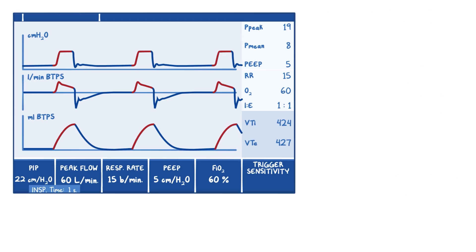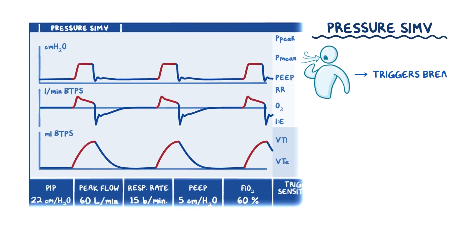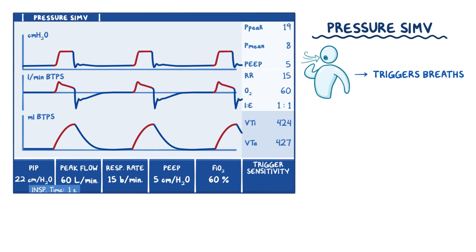So just like we were able to program the ventilator to support natural breaths in volume modes of ventilation, with pressure-synchronized intermittent mechanical ventilation, or pressure SIMV, our patient can also trigger breaths. In pressure SIMV, we'll set all the same parameters: the peak flow, the respiratory rate, the inspiration time, the PIP, and the FiO2. Except instead of volume, we're going to set our peak inspiratory pressure with that added setting of trigger sensitivity.